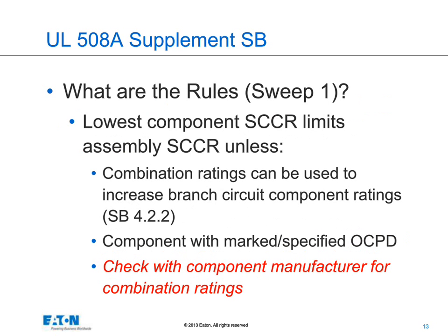When looking at the Bussmann method for determining the SCCR of industrial control panels, we use a two-sweep method. In sweep one, we look only at components — anything other than a fuse or circuit breaker: contactors, starters, switches, and controllers. We try to use combination ratings if possible, ensuring we supply the specified overcurrent device to get those combination ratings. In many cases it may not be obvious what those ratings are, so you may have to check with the manufacturer.